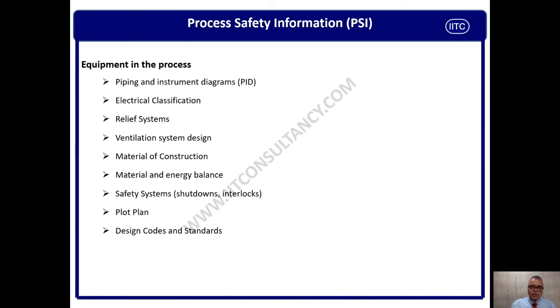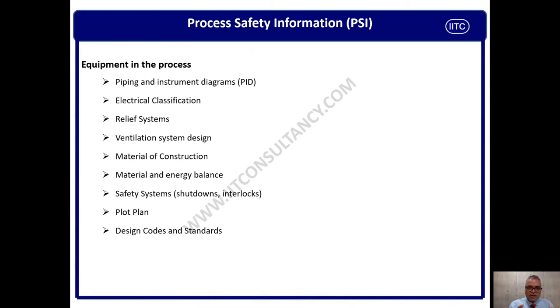We also should know the equipment in processes. Everybody in the process area, operation area, and maintenance area should be familiar with the process and instrumentation diagram, which is known as P&ID or PID. In P&ID, we know all the equipment, the flow of the processes, all the process parameters, and all safe controls — so everybody must be familiar when dealing with these kinds of processes. Regarding electrical classification — this means hazardous area classification, zone 0, zone 1, zone 2 and different classes. According to different classes, all electrical equipment must be identified, placed, maintained and monitored, because hazardous area classification equipment can create a source of ignition leading to possible fire and explosion.